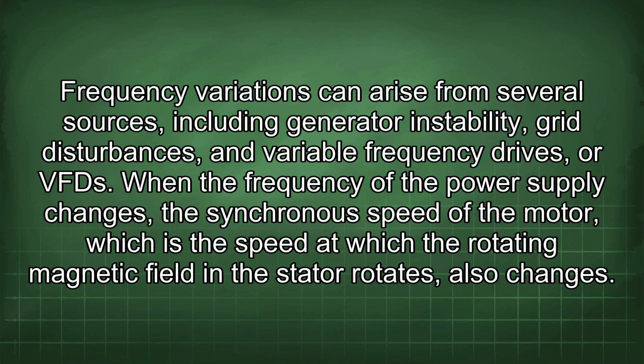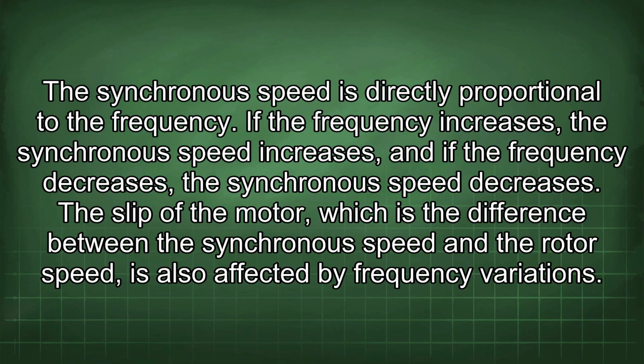When the frequency of the power supply changes, the synchronous speed of the motor, which is the speed at which the rotating magnetic field in the stator rotates, also changes. The synchronous speed is directly proportional to the frequency. If the frequency increases, the synchronous speed increases, and if the frequency decreases, the synchronous speed decreases.